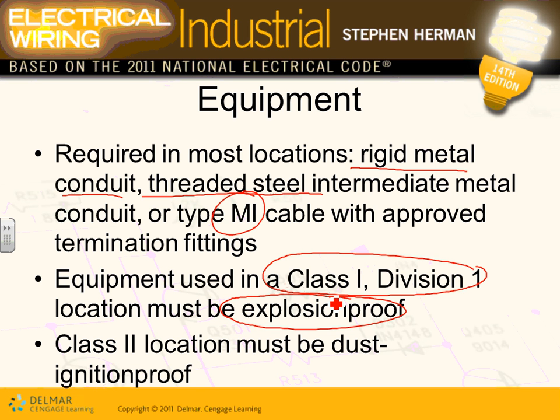Very, very expensive equipment. So if this fixture, Adam, above your head is $100, an explosion-proof one will be $500. So you try to avoid having explosion-proof equipment unless you have to. Okay, in a Class 2 location, that's in a Class 1, the gas. In the dust area, the equipment that they use is dust ignition proof. Dust ignition proof, guys, very simple.